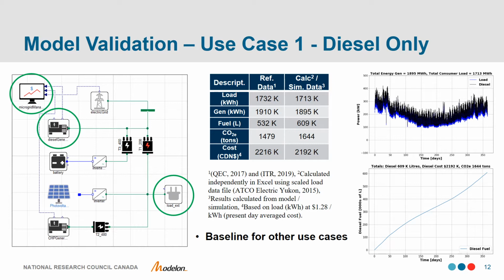When we looked a little closer, we saw that the utility actually used a fuel efficiency value that was much higher than the value that we had derived from our fuel consumption curve shown previously. A later study was identified with more recent data, which showed a fuel efficiency value that was much closer to the value that we had been using, and essentially, based on this, the diesel consumption rates were deemed to be acceptable and were retained for the remainder of the analysis.